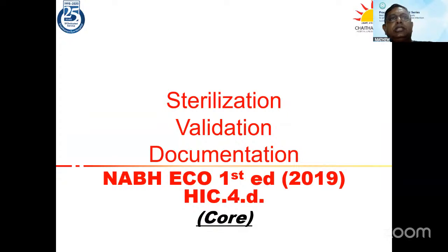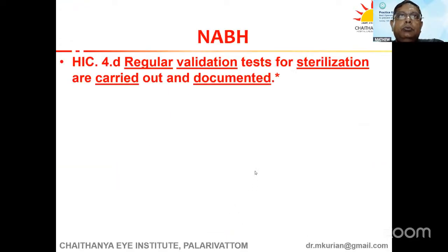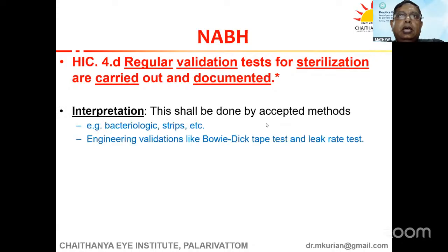So we'll be talking about sterilization, and this is in the NABH Eye Care Organization requirements. In the first edition, it is part of the HIC 4D, and in the second edition, which is due to come out now, that will be the core element, which means it is mandatory for everybody to have this, irrespective of the level at which you are operating. We talk about the requirement for regular validation tests for sterilization, and that it should not just be done, but it should be documented. And this can be done by accepted methods like bacteriological strips, engineering validations like Bowie-Dick.